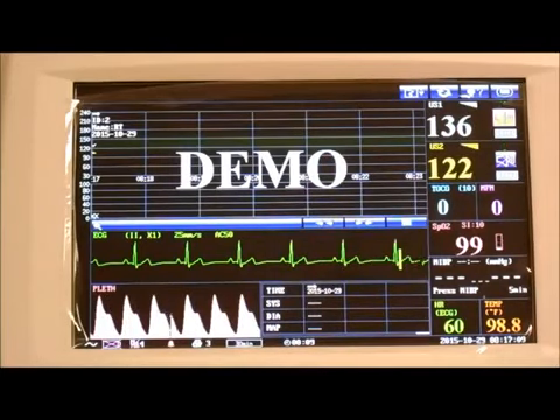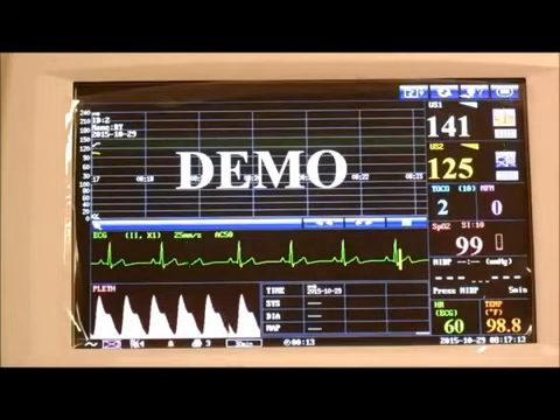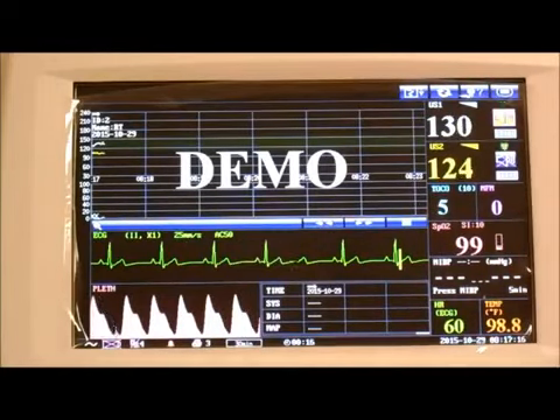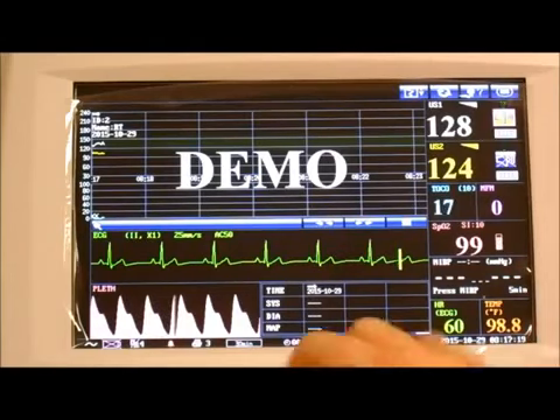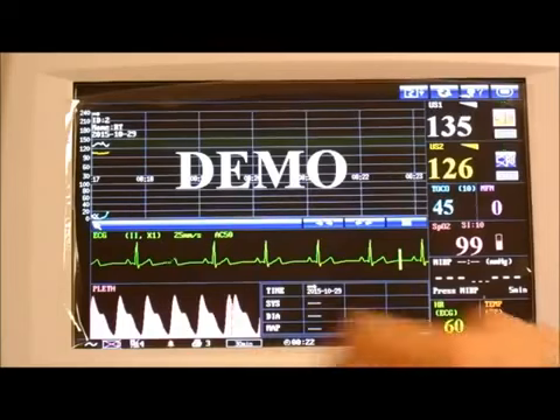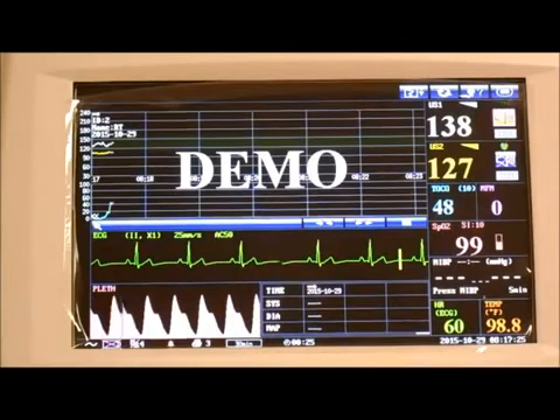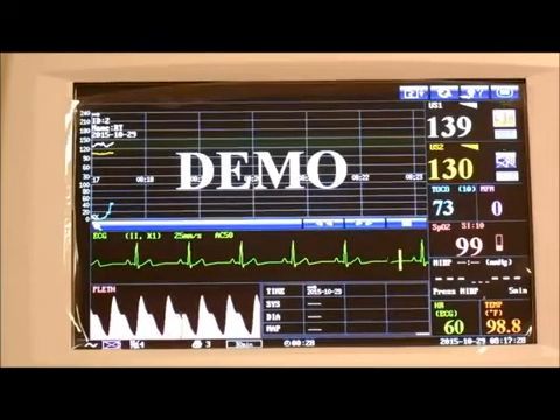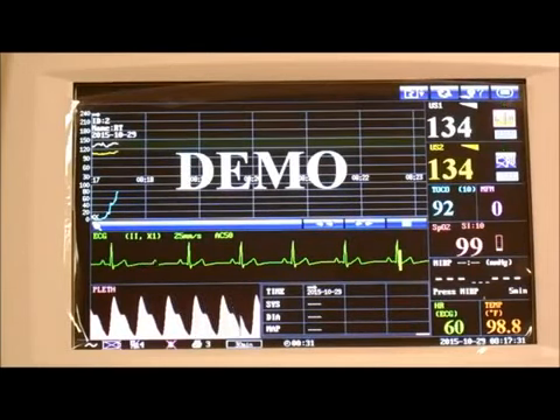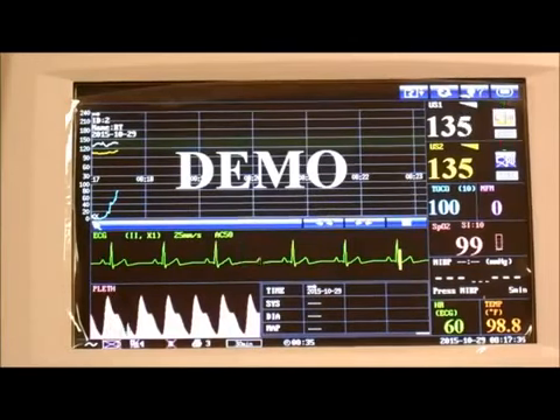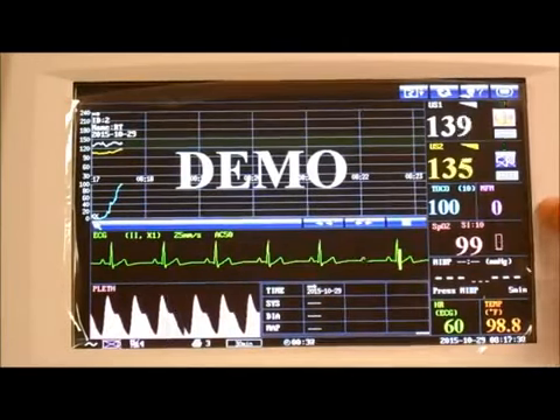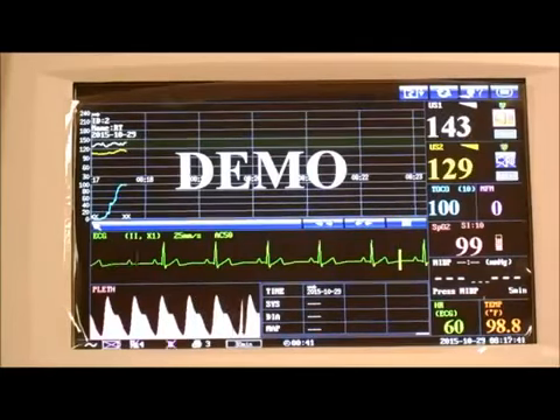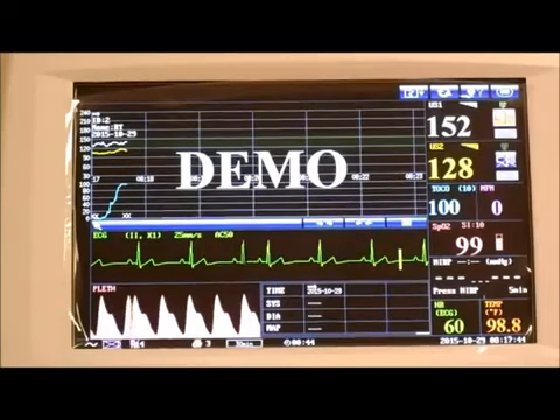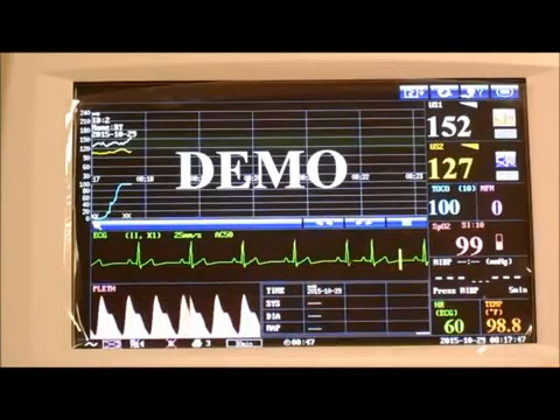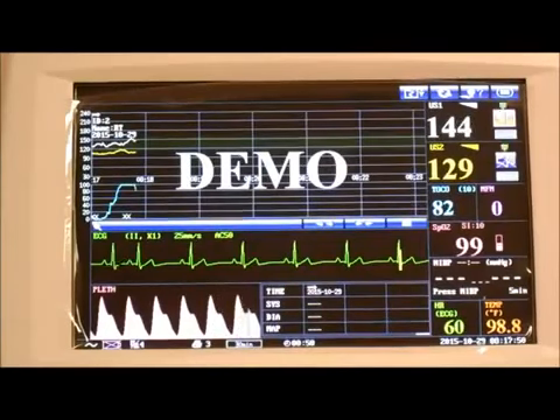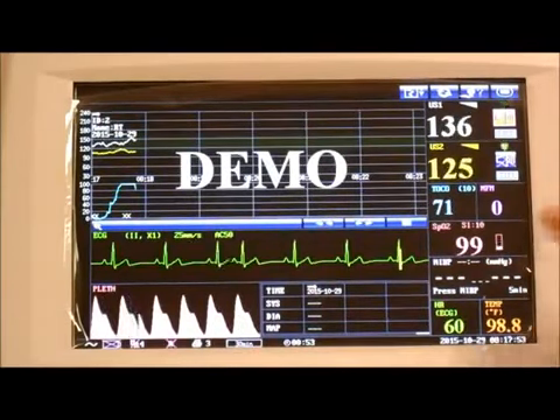Place the transducer on your patient, press the start key to start a new session. The system will automatically ask you to enter the information, and it'll start printing for 30 minutes or depending on your preferred setting. And that's it. You press the silence key to mute any alarms. If the toco transducer accidentally falls, you place it back on your patient. You press auto 0 to set it back to the baseline, because when you press the start key, it also does the auto 0 command by itself. You only do the auto 0 if it falls during a session, so that you don't have to start all over and you can bring the toco back to baseline.